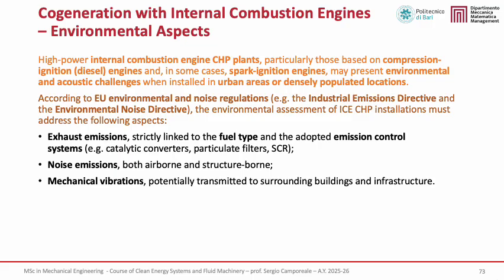According to the EU environmental and noise regulations, such as the Industrial Emissions Directive and the Environmental Noise Directive, the environmental assessment of ICE CHP plants must explicitly address three main aspects. First, exhaust emissions, which are strictly linked to the fuel type and to the emission control systems adopted, such as catalytic converters, particulate filters, or SCR systems. The SCR means selective catalytic reactors.